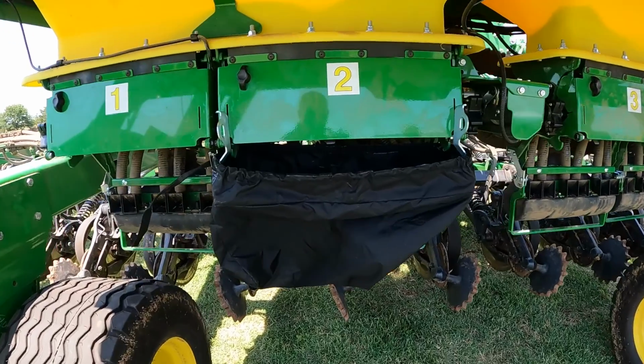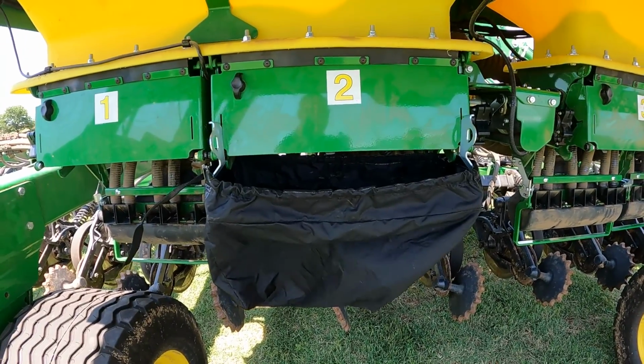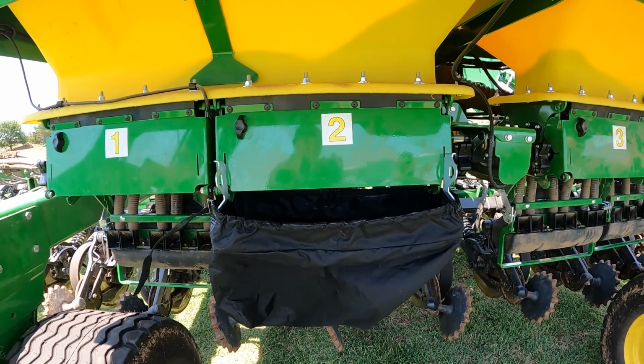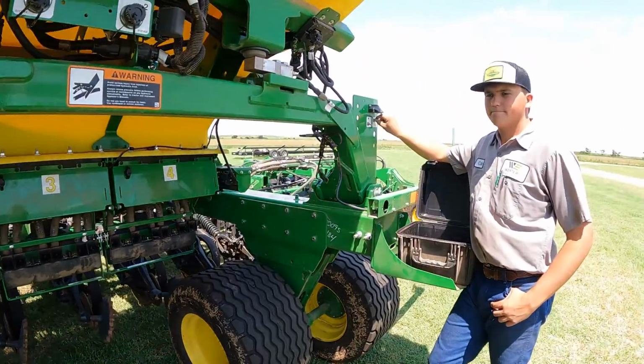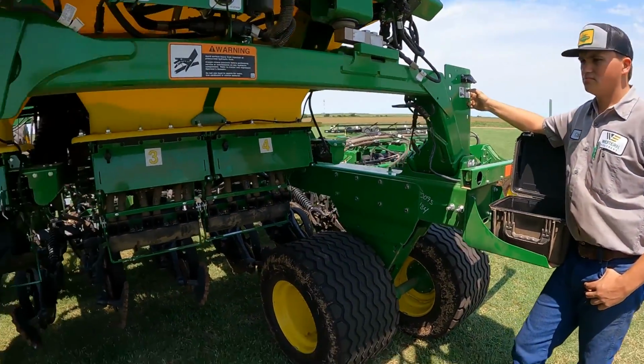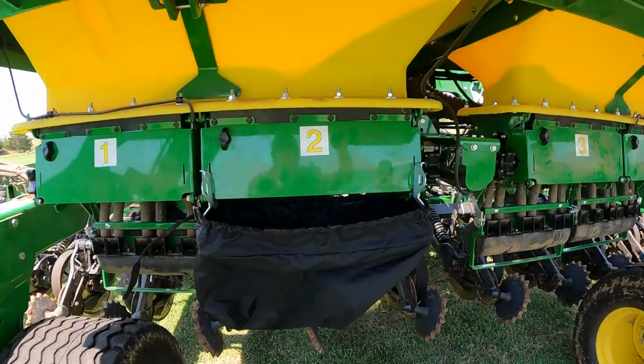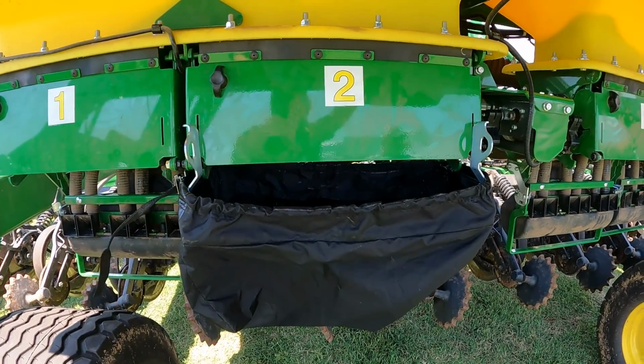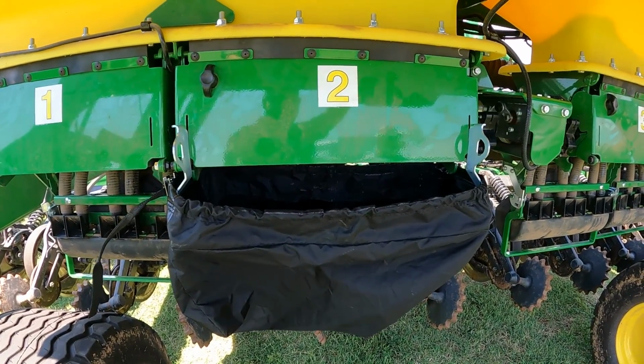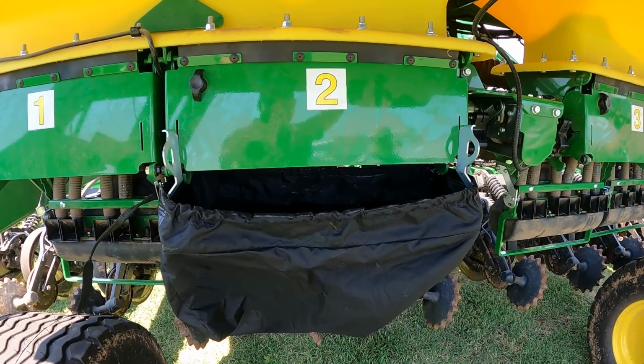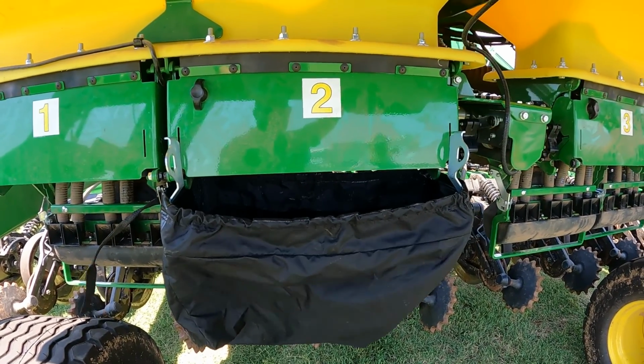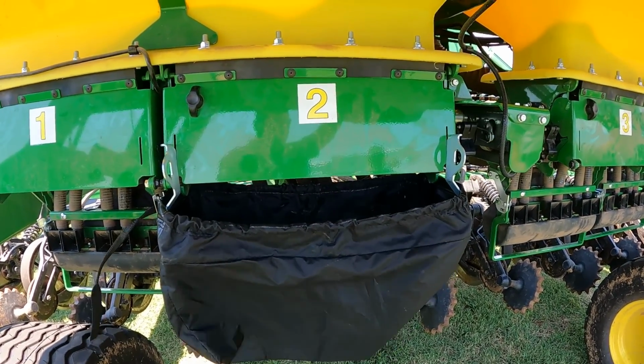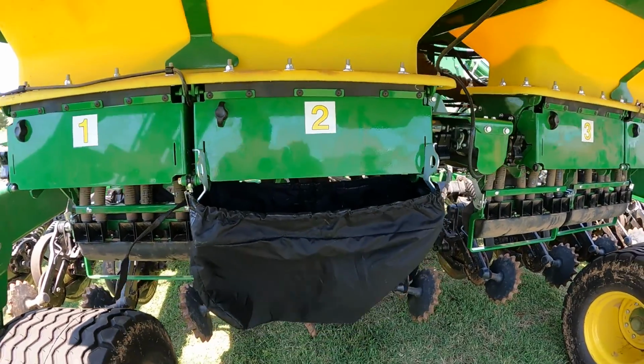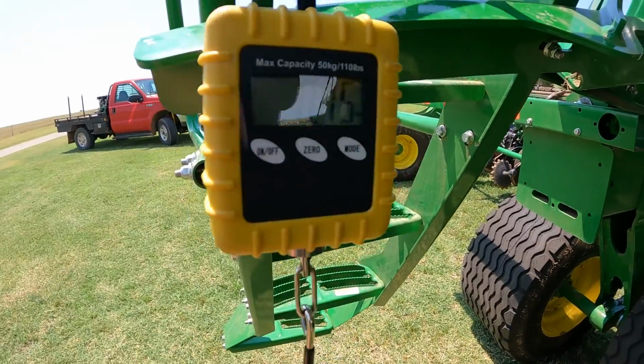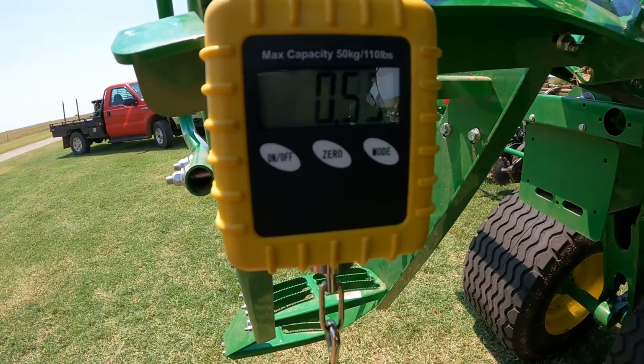So we've got our bag hung on our left center meter that we're going to verify, and Caleb's going to hit that switch. The procedure says to hold down the calibration switch, or meter rotation switch, until the meter stops turning, and then we'll weigh the bag. If we've got everything right we should come out with 3 pounds, and we come out with 0.75 on our scale weighing our product.